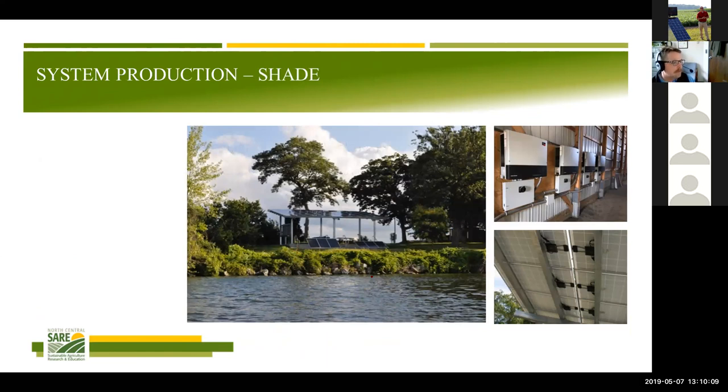Shade's a problem, because people can think they can put up solar and then they don't think about the trees. Sadly, installers sometimes estimate production and assume there will be no shade. Then you go out to the site and sure enough, there are three big trees causing a problem. Now, Ohio State did figure this out, maybe because they needed to cut the trees or because of the solar, but some of these trees have been removed since then. This was built at an Ohio State research station.